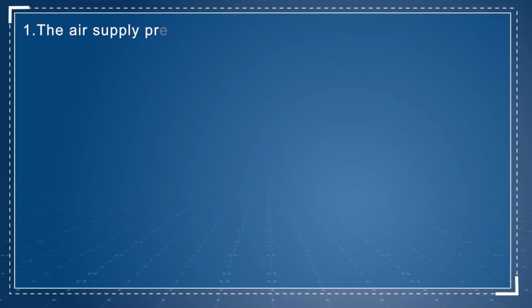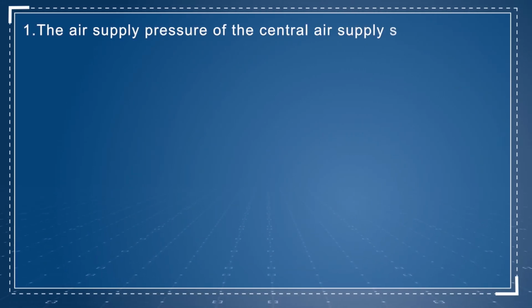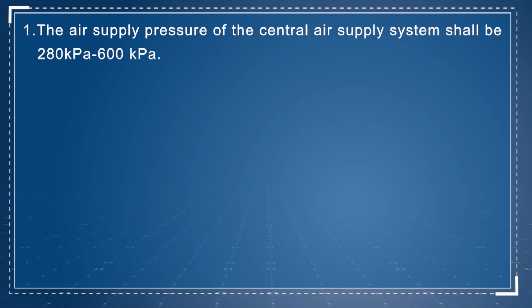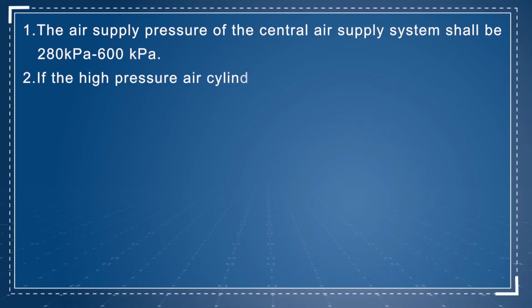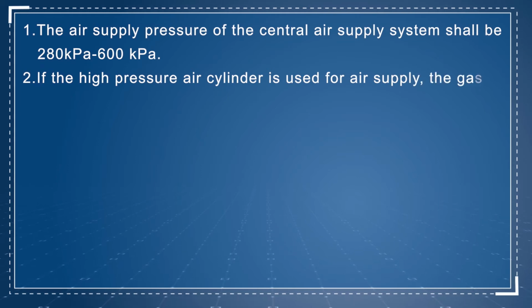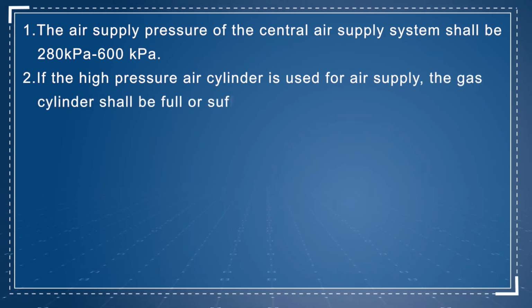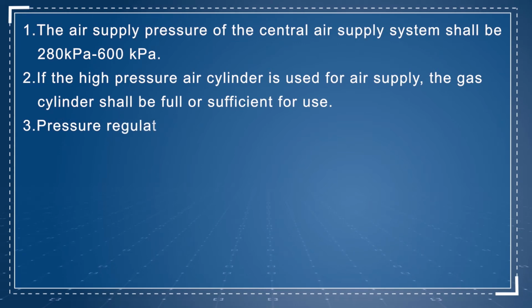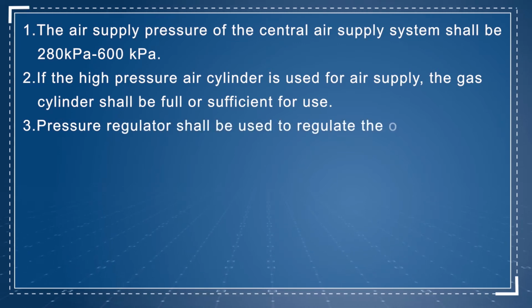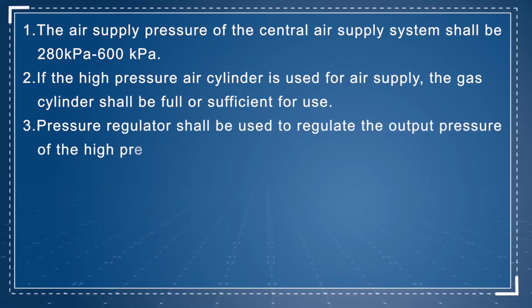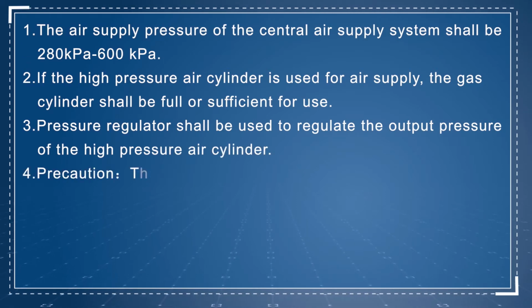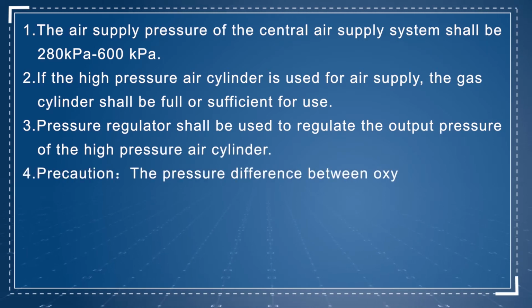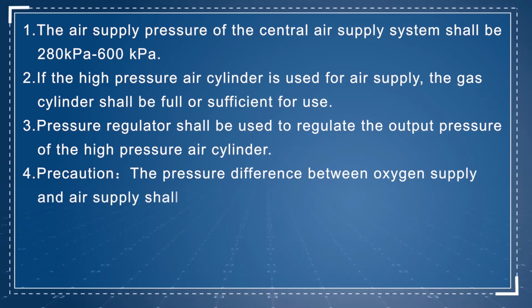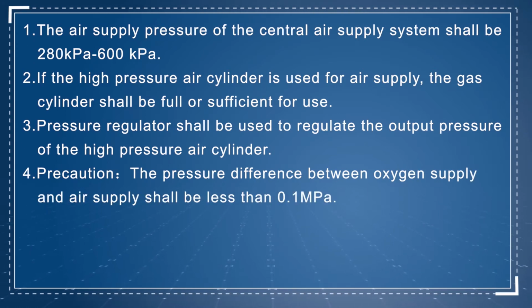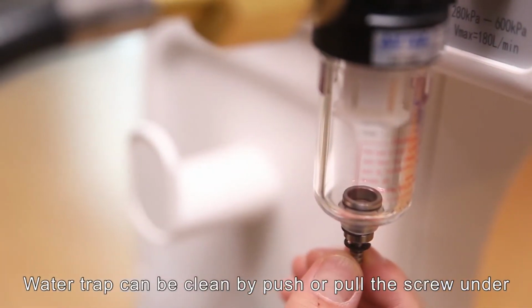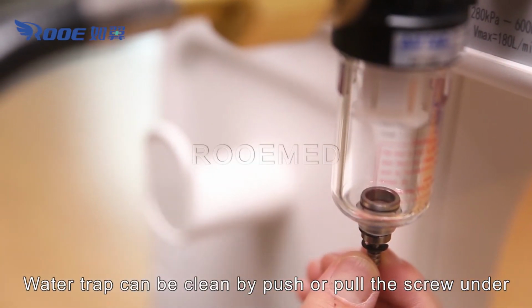1. The air supply pressure of the air supply system shall be 280 kPa to 600 kPa. 2. If the high-pressure air cylinder is used for air supply, the gas cylinder shall be full or sufficient for use. 3. A pressure regulator shall be used to regulate the output pressure of the high-pressure air cylinder. 4. Precaution: the pressure difference between oxygen supply and air supply shall be less than 0.1 MPa. The water trap can be cleaned by pushing or pulling the screw.